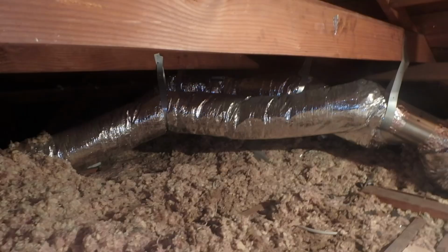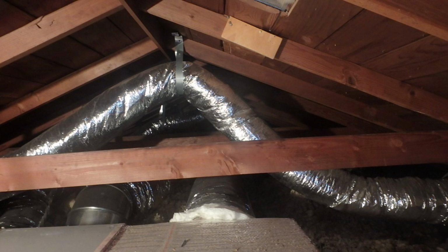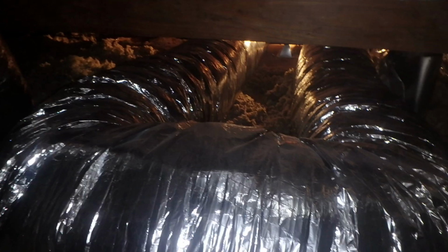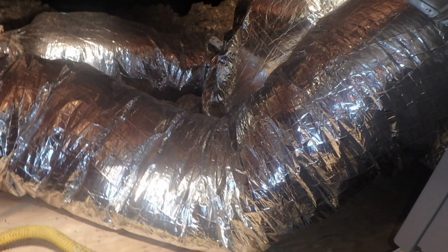So if you look here, we got a system that's in the attic that has ducts along the ridge of the roof, which gets really hot, really cold, above the insulation line. The insulation's really low, not a lot of it in there. They ran ducts in a crazy way in circles. They kinked ducts for no real reason, just because that's the length they had. These systems don't work very well.